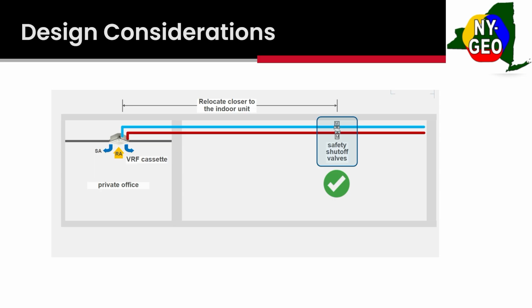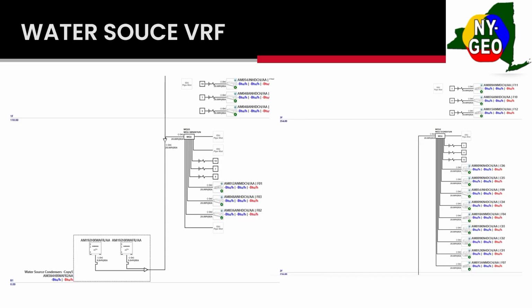It's not an easy calculation because it has to do with a lot of refrigerant pressures, how much volume is in the pipe, how much volume is in your evaporator coil. So the manufacturer should be providing you that information on how much charge is between that valve and your indoor unit. Here's an example of a water source VRF system. This one's kind of funky, the way we have to do it. This is basement, first floor, and I split it up, second and top floor. So this is a typical design here.